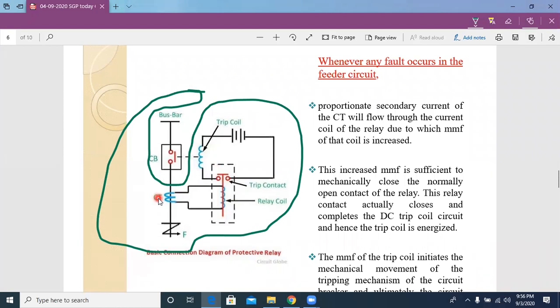Now in this diagram we can see some components like the current transformer, and this current transformer secondary is connected to the relay coil. If the activating quantity is current, then this relay coil we call a current coil. If the activating quantity is voltage, then in this place we use a potential transformer, and the potential transformer is connected to the relay coil, and that relay coil we call a voltage coil.